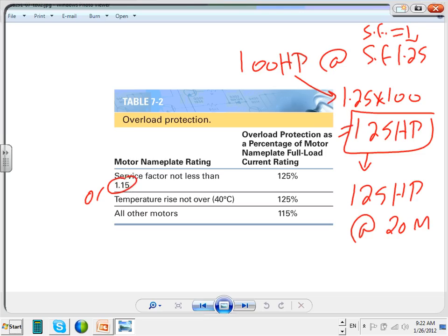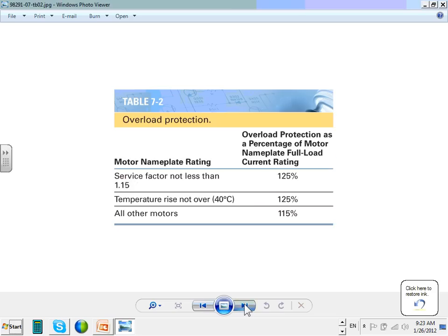So you probably see a lot of, especially cooking appliances and stuff, maybe have a high one. It's more for the machine. A lot of machines have at least a 1.15 service factor. They allow you to overload it. Rush hour on the equipment. Too much pressure for a short amount of time though. So if you look, it allows you to overload the motor, besides your overload being higher, meaning you can overload the motor and the wires are not going to start burning. Make sense, Nick? No? Yeah. So that's my overload. Moving on.